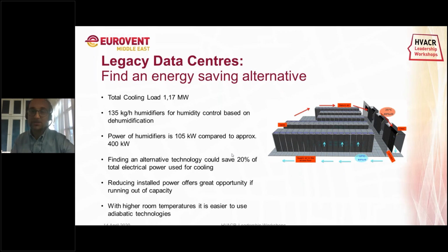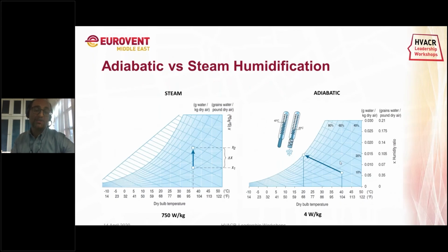So if you have the possibility to use an adiabatic technology, which is basically using water spraying, or other ways to put air in contact with water, if you are able to achieve this, the air humidification happens using the energy of the air itself. So you have an effect. The adiabatic effect is something that I'm sure you all know. If you are able to achieve this, you could humidify and at the same time reduce temperature, but on top of that, you're not going to use a lot of energy. One technology, talking about technologies, that is becoming very popular is ultrasonic humidification.